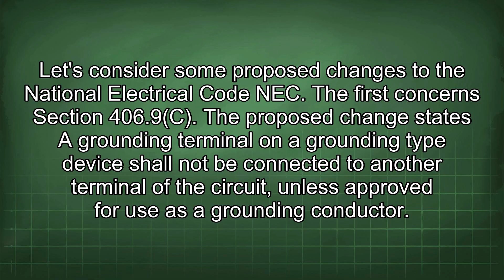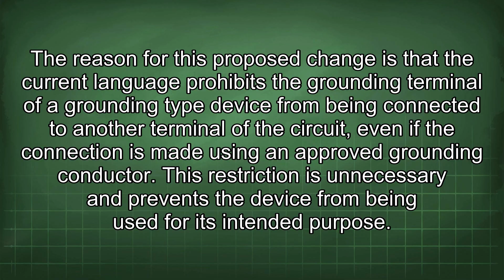The reason for this proposed change is that the current language prohibits the grounding terminal of a grounding type device from being connected to another terminal of the circuit, even if the connection is made using an approved grounding conductor. This restriction is unnecessary and prevents the device from being used for its intended purpose.